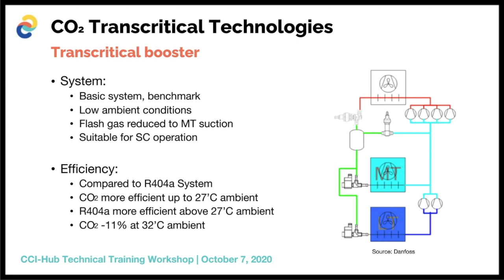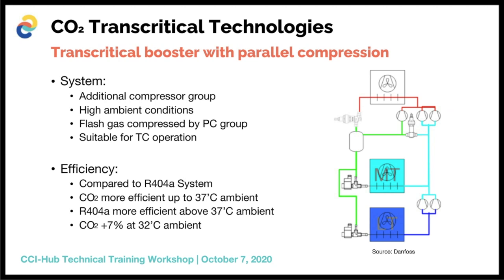One of the first steps in improving efficiency is the introduction of a parallel compression system. Instead of the flash gas created in the receiver vessel being reduced to medium temperature compressor suction and compressed from a lower pressure to discharge pressure, this flash gas is now compressed by an additional compressor called the parallel compression set, operating with suction pressure equal to receiver pressure.